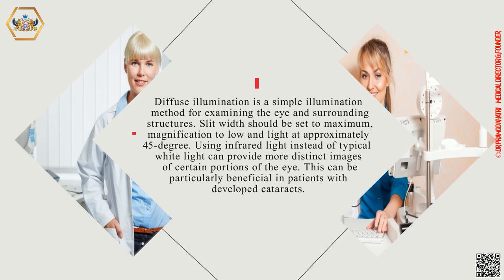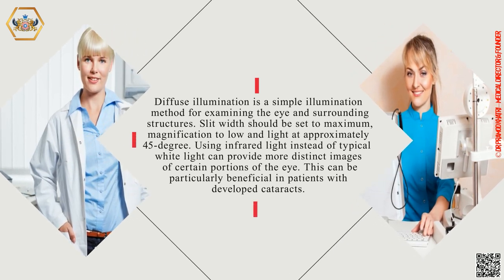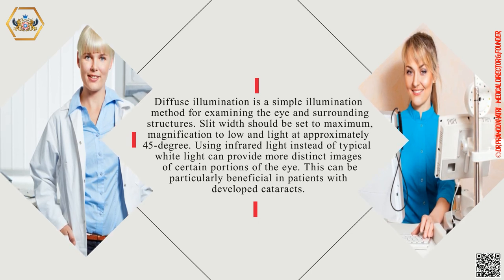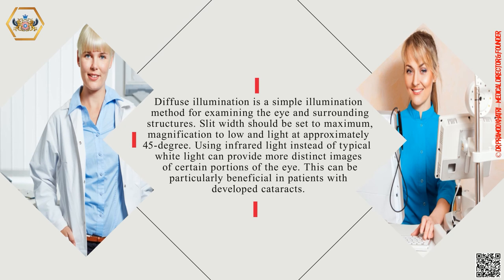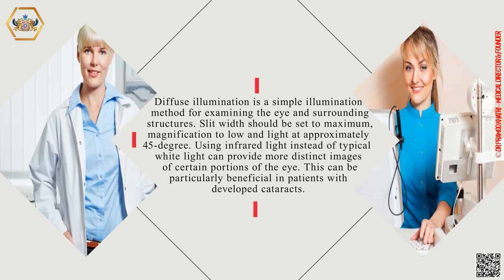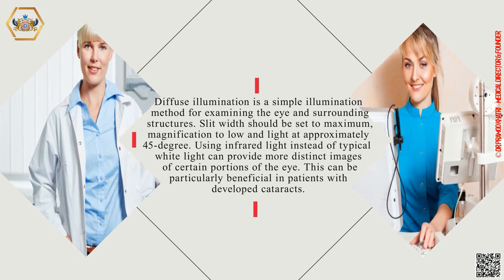Diffuse illumination is a simple illumination method for examining the eye and surrounding structures. Slit width should be set to maximum, magnification to low, with light at approximately 45 degrees. Using infrared light instead of typical white light can provide more distinct images of certain portions of the eye, which can be particularly beneficial in patients with developed cataracts.